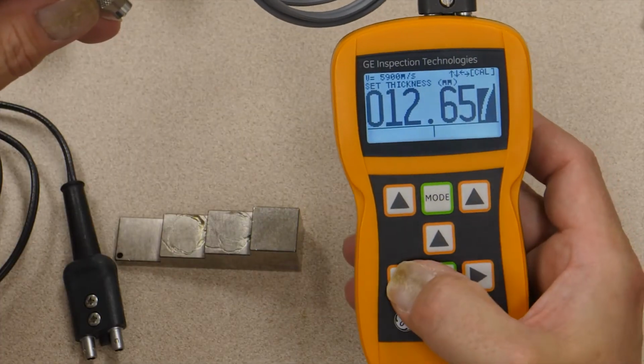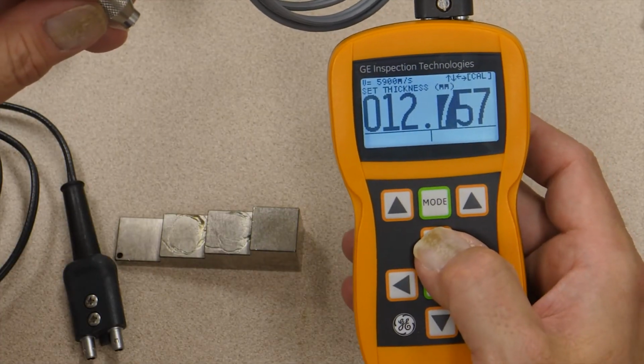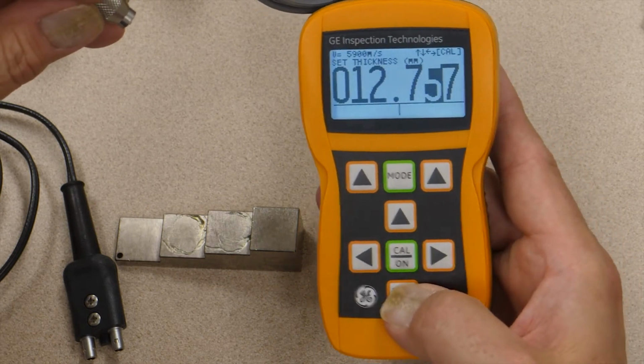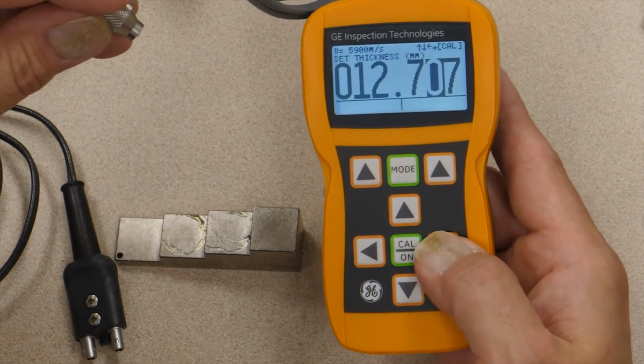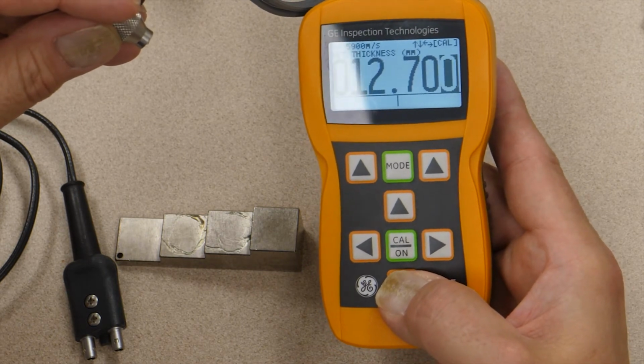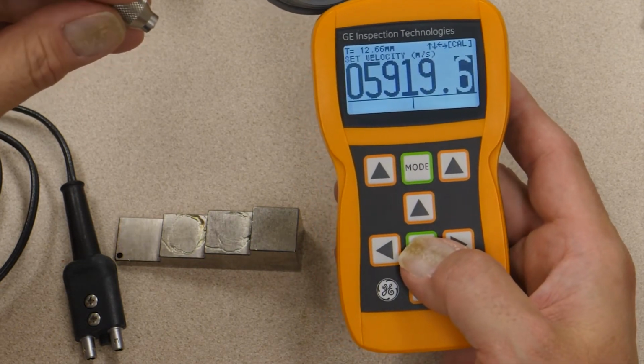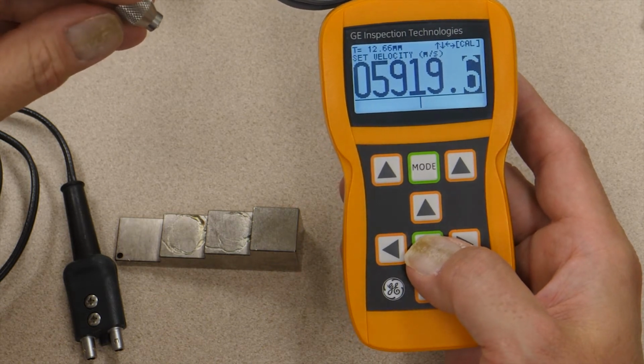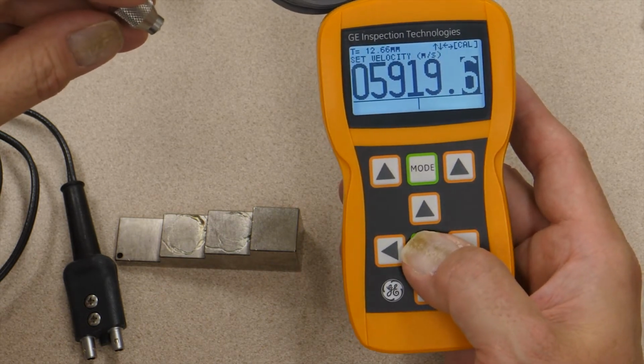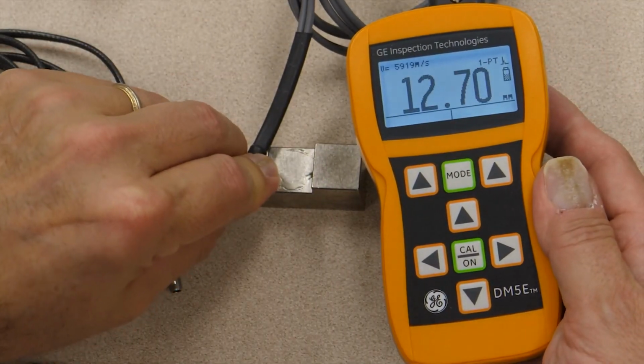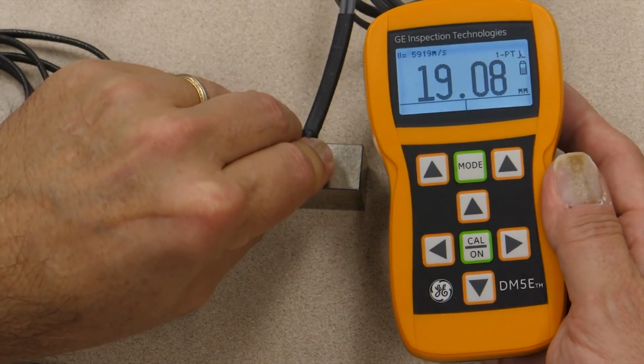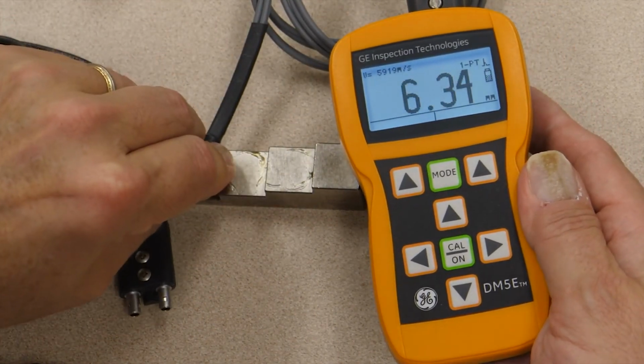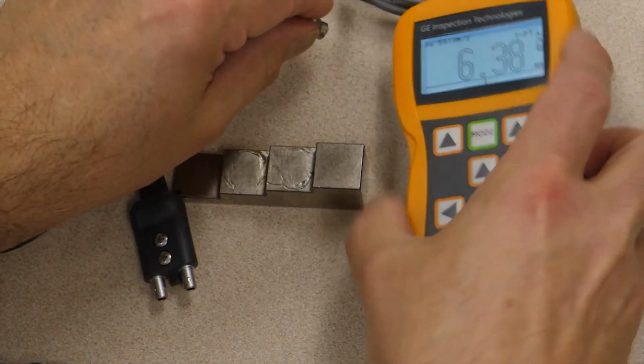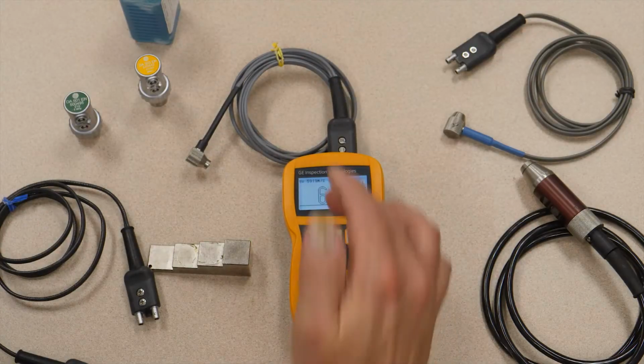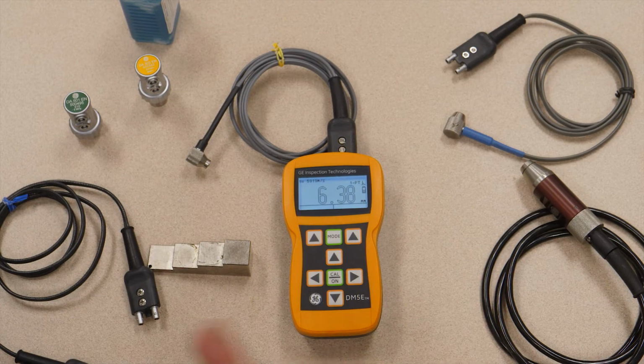So 12.65 millimeters. Let's say I know that's 12.700 millimeters. I can make my adjustments. And it tells me that gives a calculated velocity of 5,919 meters per second. Fully believable for carbon steel, 12.7, 19 millimeters, 6 millimeters. Okay. So that's how you select the probe and step through a simple calibration.